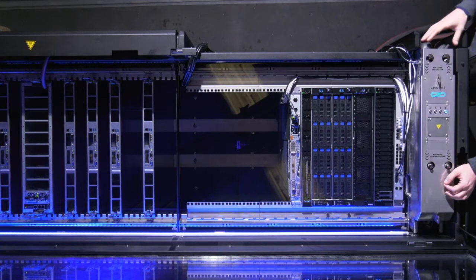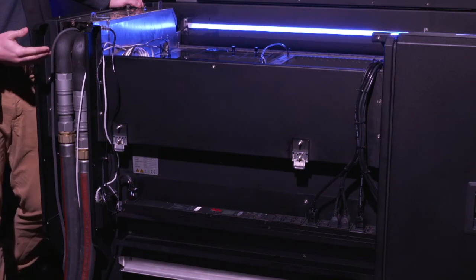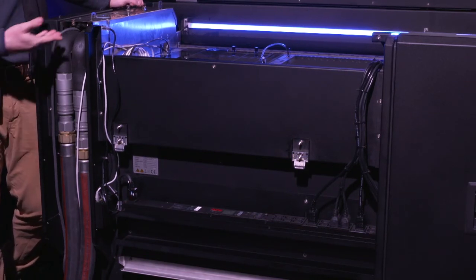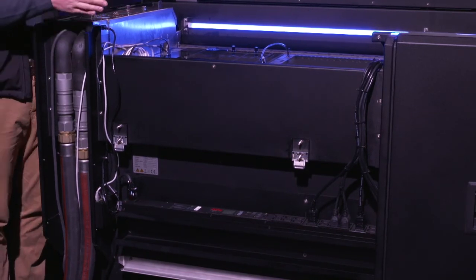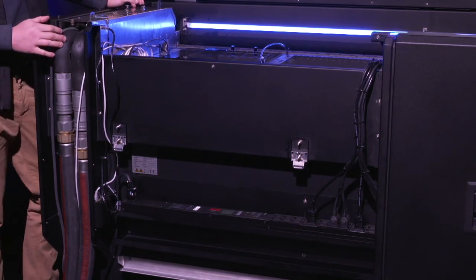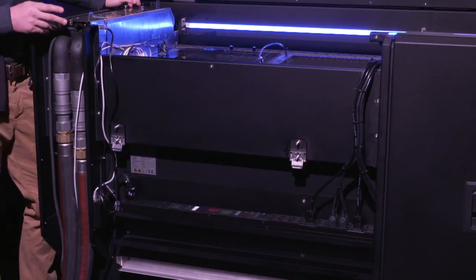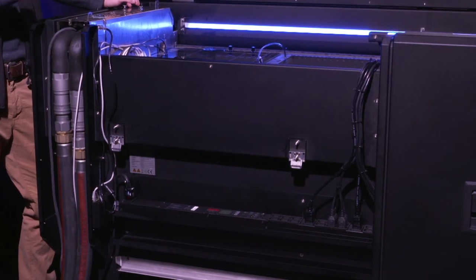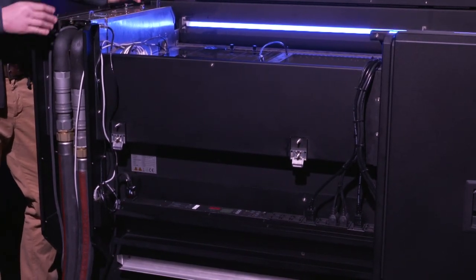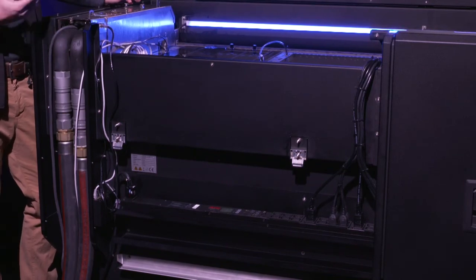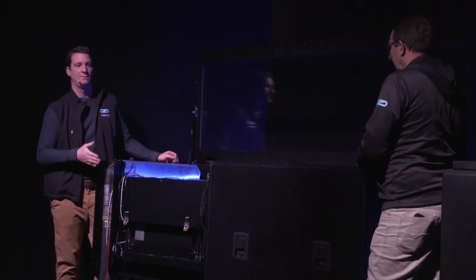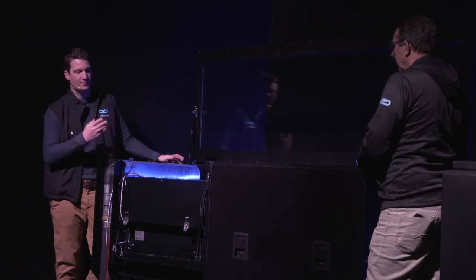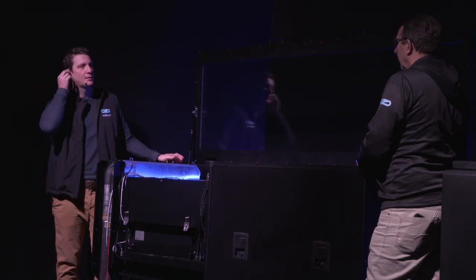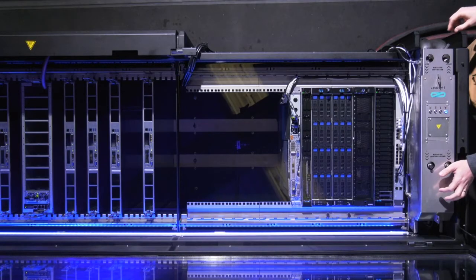But another thing that we see in the dry zone is the connections to the CDU. Now the connections to the CDU occur above the fluid level, so this tank does not have a single hole in it. And we actually have a couple of options when it comes to tanks with a single hull and a dual hull environment, meaning that we have full secondary containment of the fluid built into the tank.